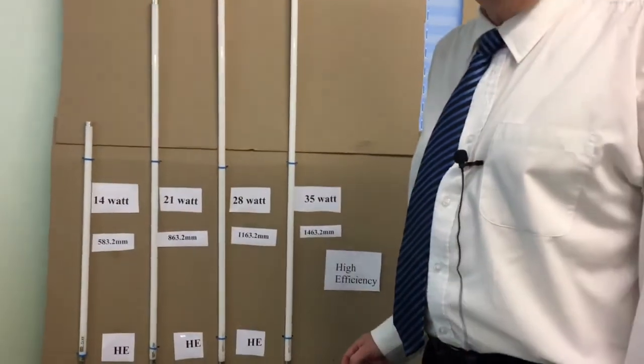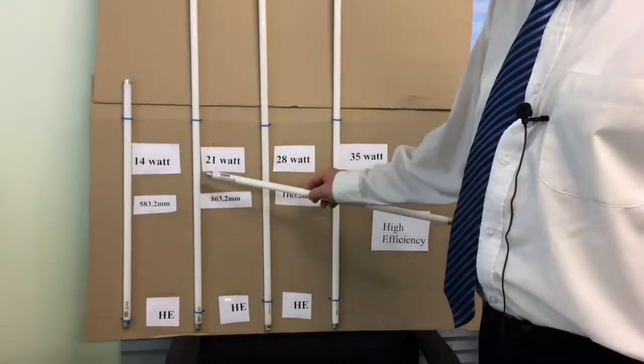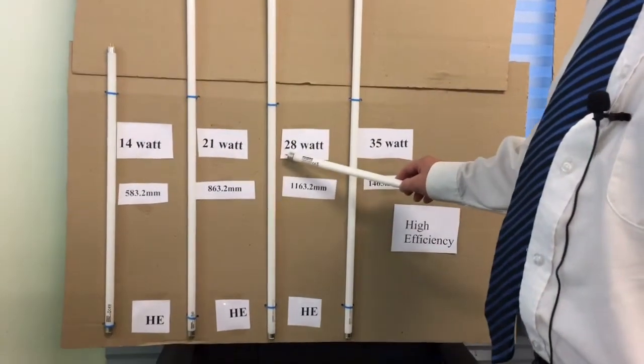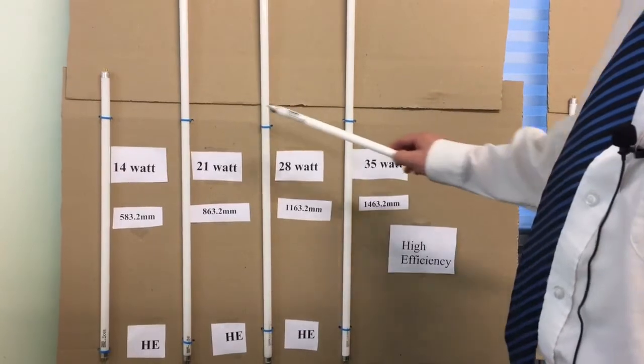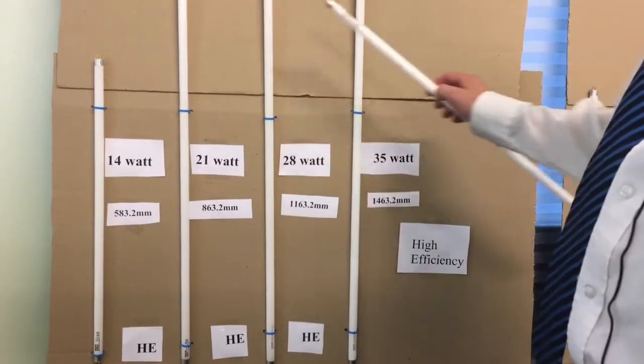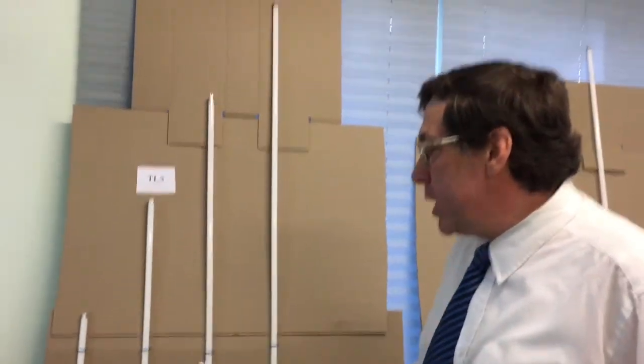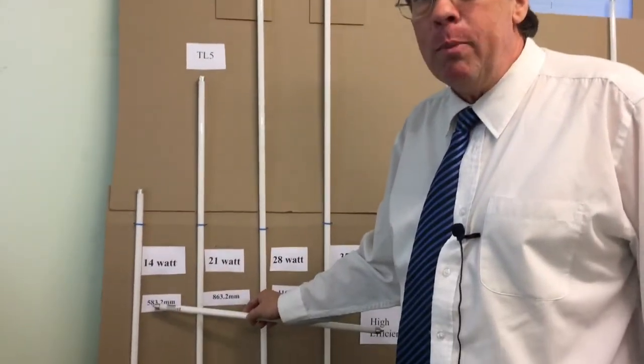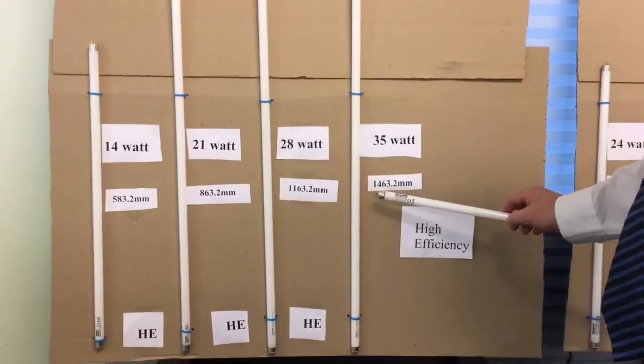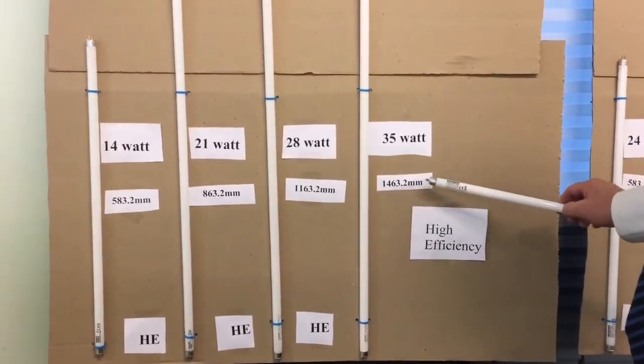With the high efficiency model, it comes in four wattage types starting off at 14 watt, 21 watt, 28 watt, and 35 watt. The lower wattage is the shorter and the higher wattage is the longest one. They start off at 583.2 millimeters and they go up to 1463.2 millimeters.